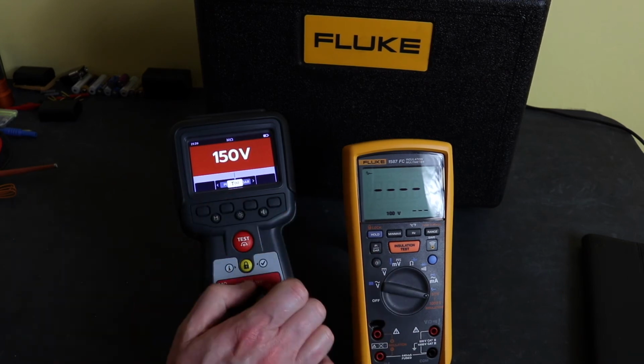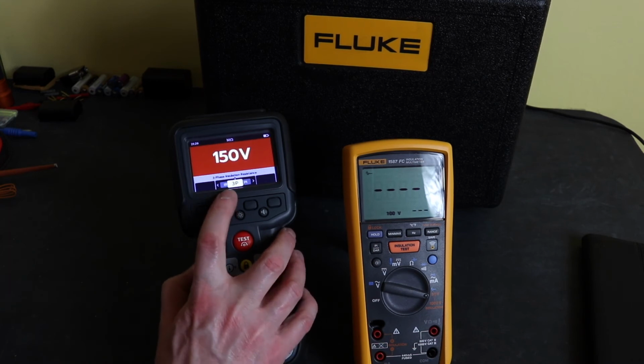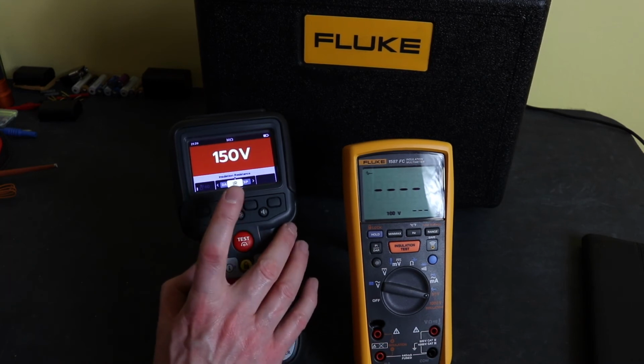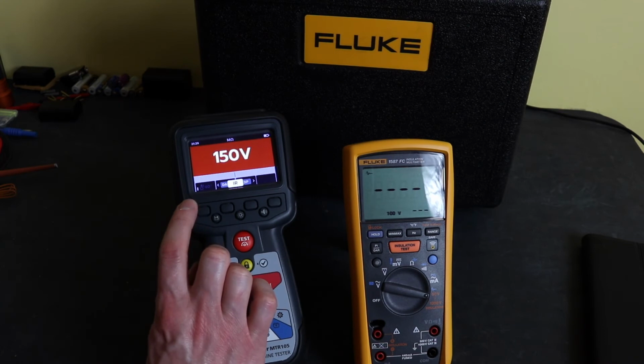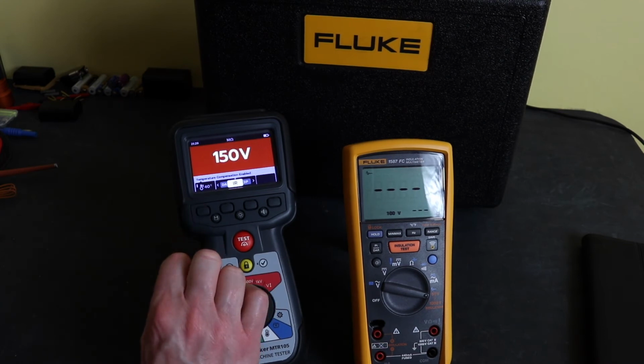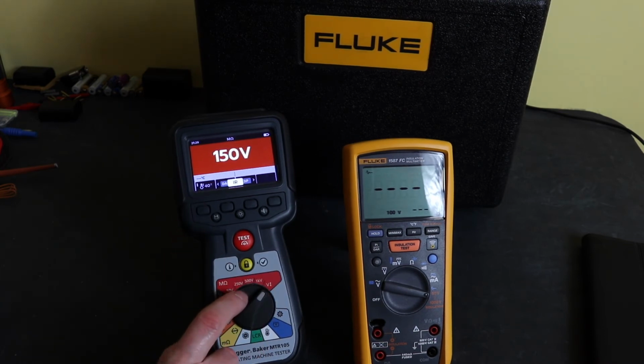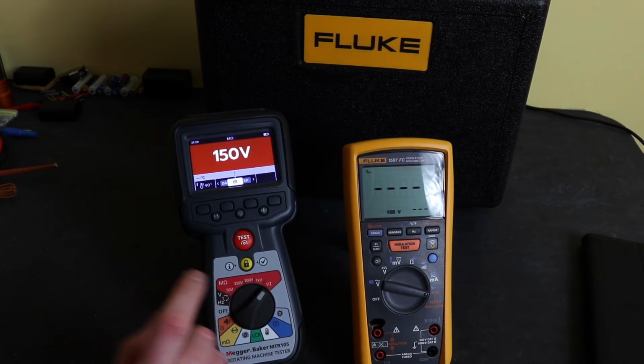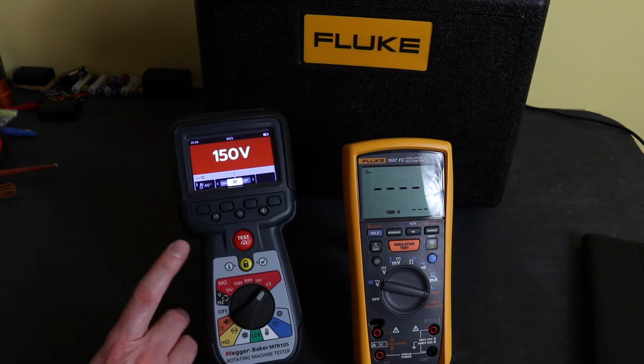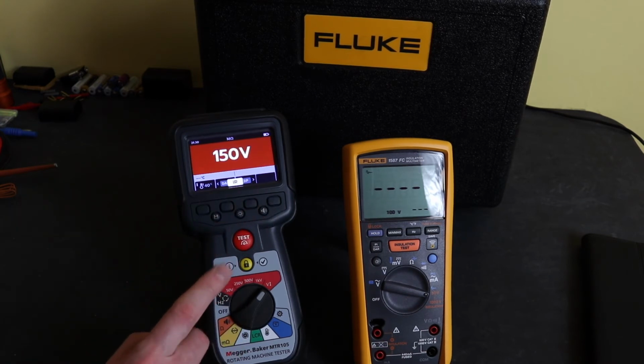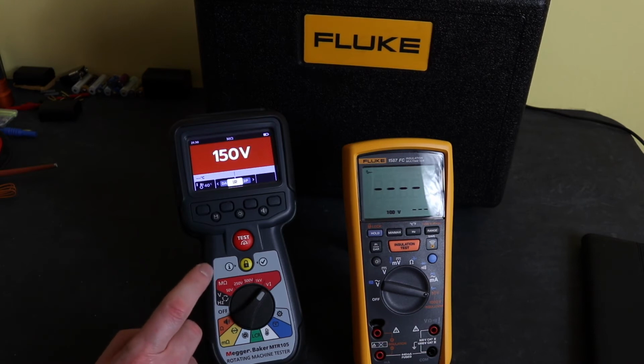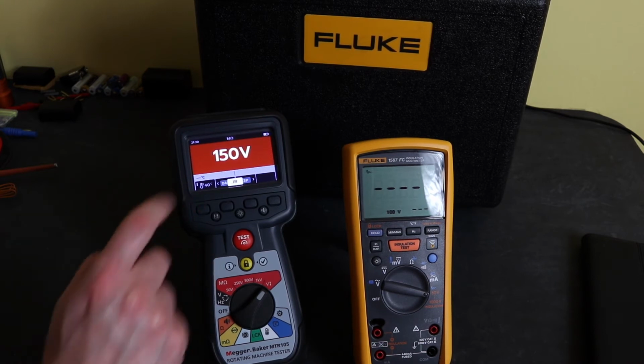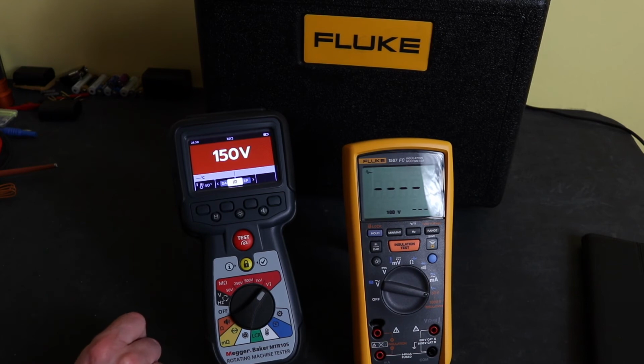What you also get with this instrument is a three-phase insulation test and also a temperature compensated test, so that when you test the winding, you can measure the temperature of the winding with the thermocouple, and it will do an automatic calculation based on the temperature of the winding and the desired temperature that you want it to adjust the reading to, which is usually 40 degrees C for the IEC standard.